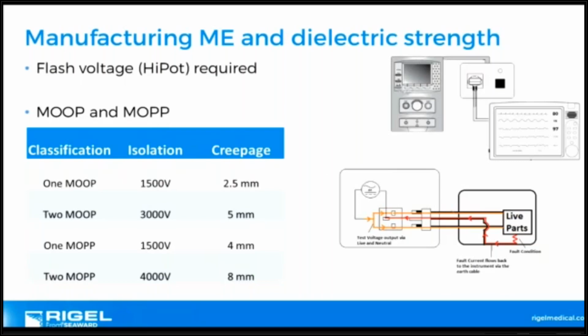More importantly, what's happening here is the dielectric strength goes between, let's say this is our earth or ground, and let's say this is our live or hot and neutral, and these are going into the actual device here, the plug. But what we're doing is live and neutral are shorted together, and we put the voltage, whether it be 1500 volts, between the ground or earth point of your plug and live and neutral. So that's just a little bit of an example of how you go beyond the normal electrical safety test. But this is only type testing, stress testing, but that is 60601, not a recurrent safety test. It shouldn't really be part of your preventative maintenance schedule. It's for manufacturers to do.